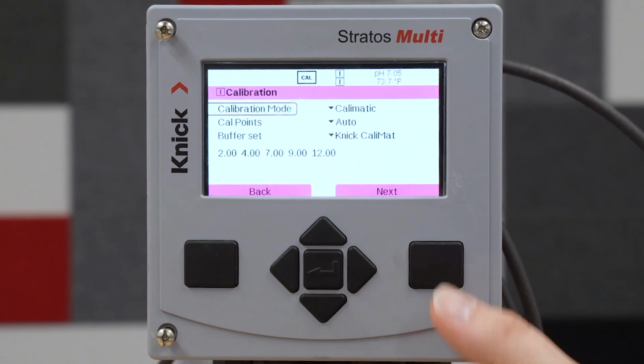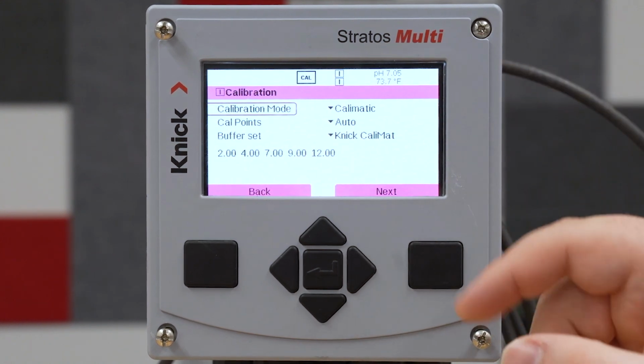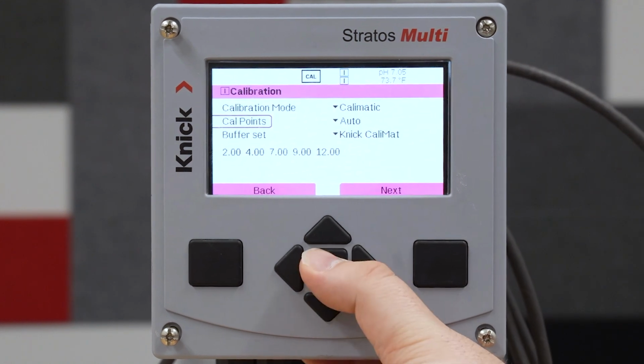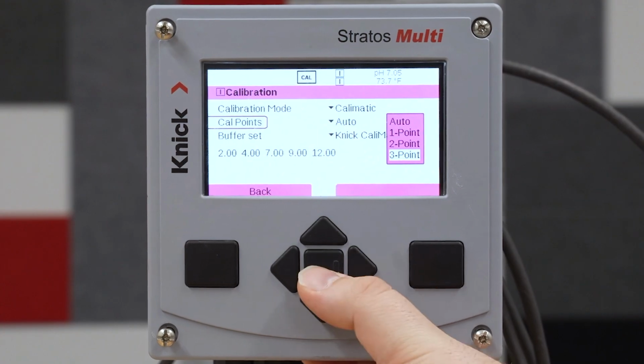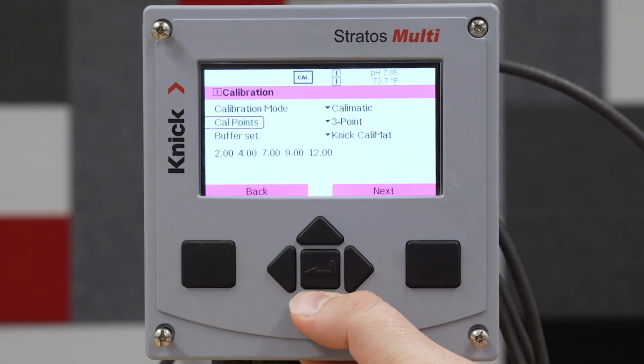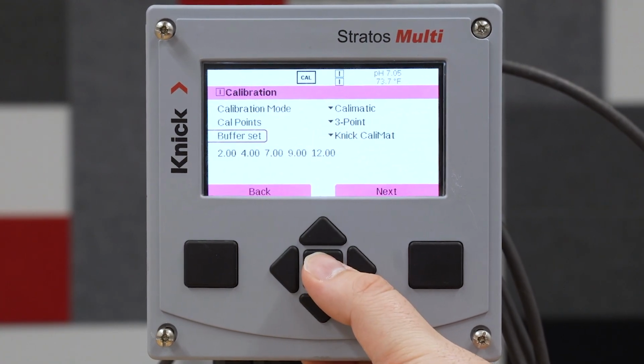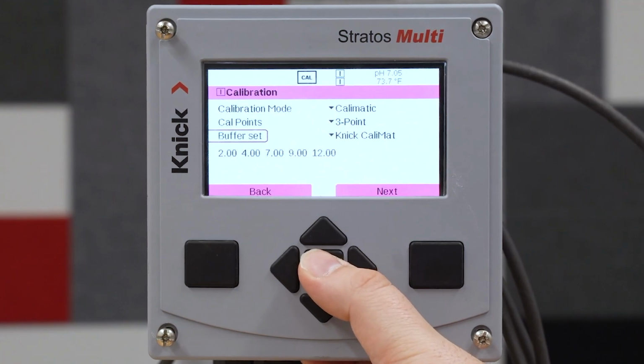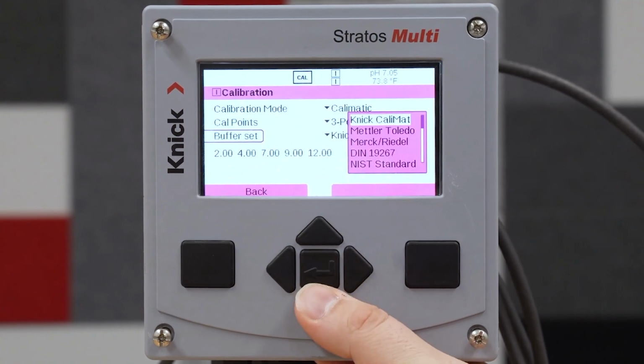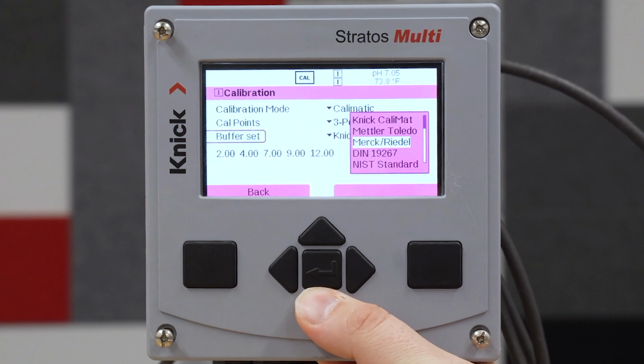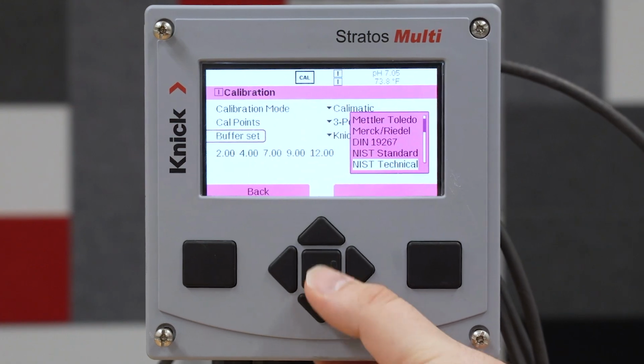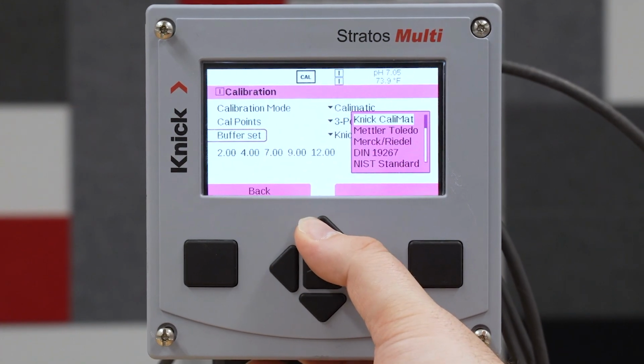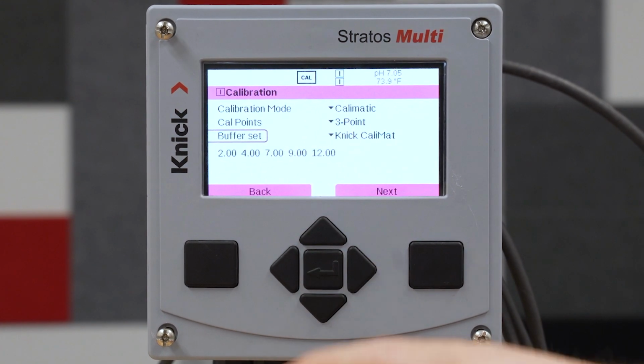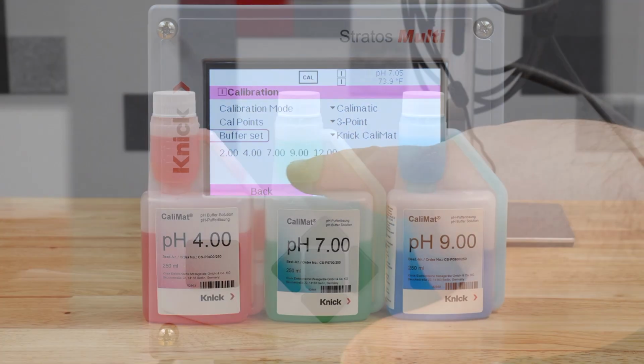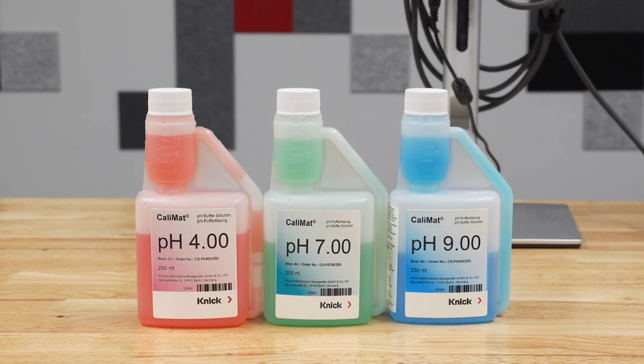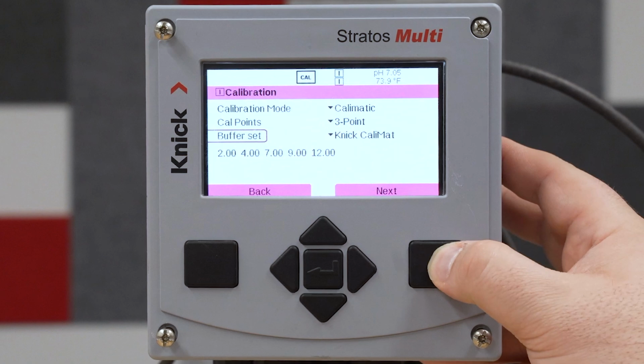We're going to choose the Calimatic calibration mode. Cal points, we're going to set for 3 points. And then for our buffer set, we're going to choose the Knick CaliMat because that's the buffer solution we have. If that's not what you have, then you can go ahead and choose one of the already pre-installed calibration solutions. Verify that we're going to use the 4, 7, and 9 of the Knick CaliMat solutions. And we're going to go through next.